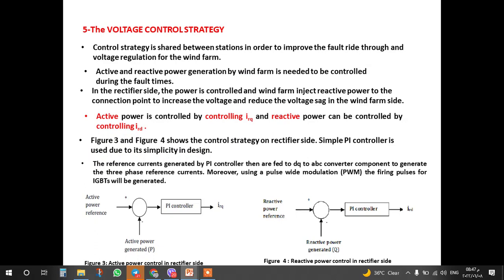The voltage control strategy for this research is: the control strategy is shared between stations in order to improve the fault ride-through and voltage regulation for the wind farm. Active and reactive power generation by the wind farm needs to be controlled during the fault times. In the rectifier side, the power is controlled and the wind farm injects reactive power to the connection point to increase the voltage and reduce the voltage sag on the wind farm side. Active power is controlled by controlling Iq, and reactive power can be controlled by controlling Id.